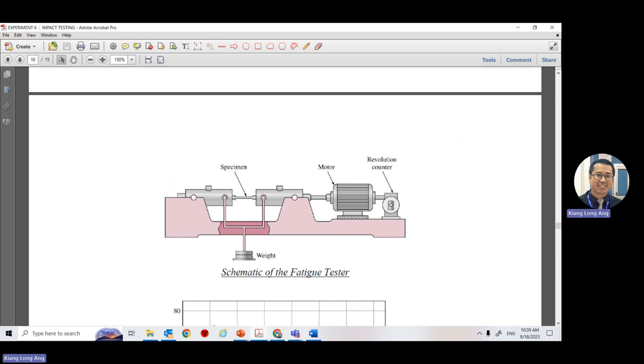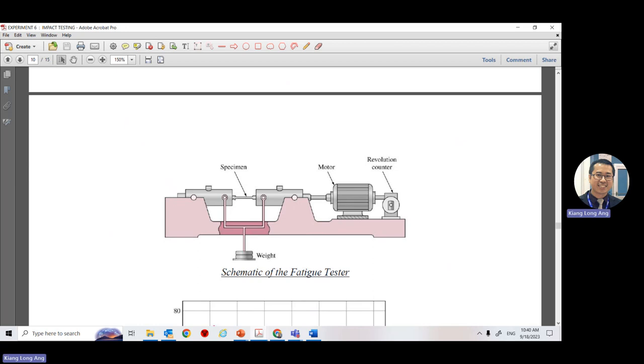There is a counter here — each revolution of the motor increments by one. Once you mount the sample, press start and it will run until about 1000 or 2000 revolutions, taking maybe three minutes. It is very noisy. The machine will stop automatically. Then switch off all the power and take the sample. For this experiment, remember to take photos before and after.